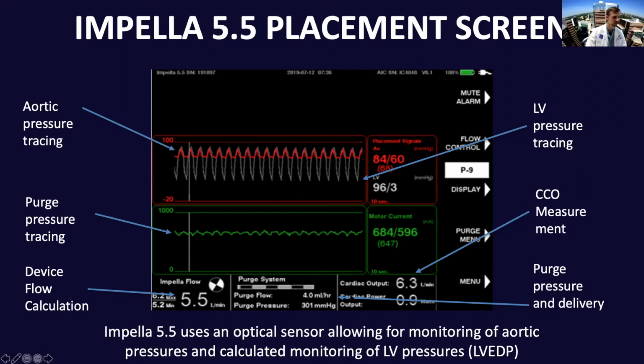So similar rest of the screen to the other devices, with a flow always in the left lower corner, purge fluid being in the middle here and actually providing a pressure for the purge. So that should be monitored very closely as well to observe for any type of presence of clots within the device that might be obstructing flow of that fluid into the motor.